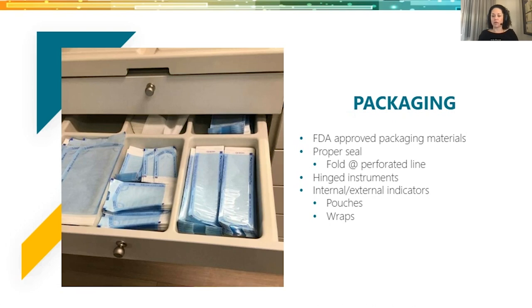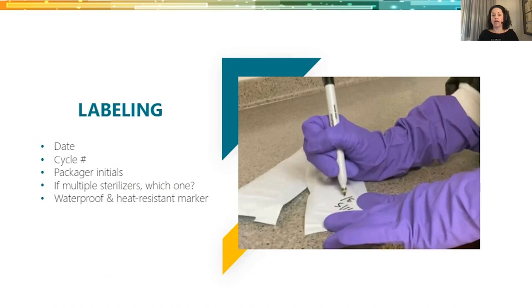Regarding hinged instruments: you cannot have them closed tight in the pouch because the closed portion — like on hemostats — is not exposed and therefore not sterilized. Labeling is required by the CDC and is a common violation. Labeling allows you to track errors and, if your autoclave malfunctions, you can collect all unsterilized pouches or cassettes from circulation so they're not used on patients. Unwrapped instruments stored loosely in drawers — like XCPs — is an infection control violation. If autoclaving anything unwrapped, it must be used immediately for the current patient; otherwise it needs to be pouched or wrapped.